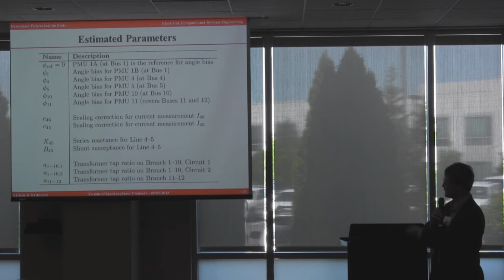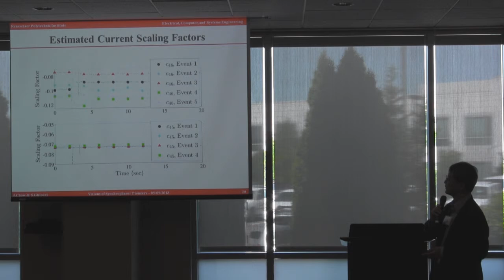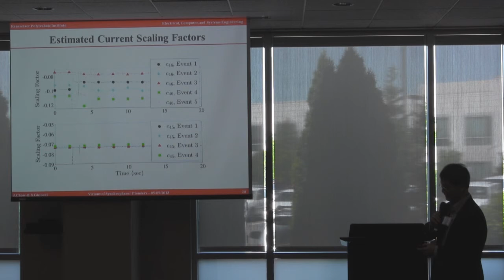So we tried this out, and these are some of the results. For example, the angle biases are small, between like 0.2 degrees. Current error, in the two lines that we have, was not really calibrated well. It's nothing to do with the PMU, but it's the calibration of the CTs. One of them is consistently off by 7%, and the other one is off by about 10%. And we actually can estimate the tap as well.